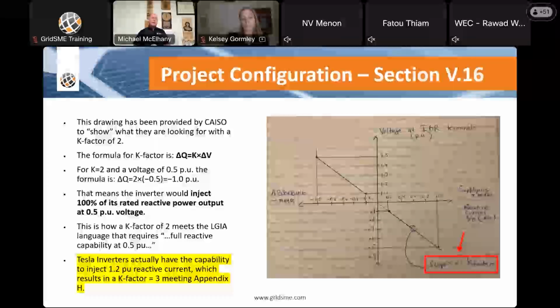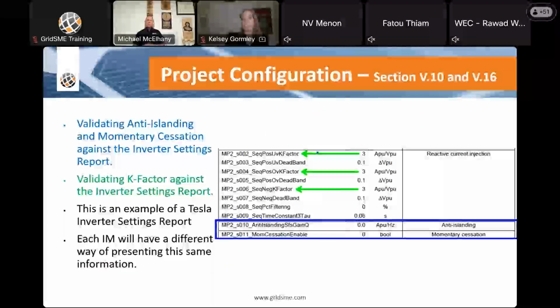The next slide has a couple of examples on how you determine whether a particular inverter has anti-islanding disabled. In this particular one, in the blue box on the bottom, it's got anti-islanding with a 0. That means it's disabled. Momentary cessation has got a 0. That's disabled. With other inverter manufacturers, you have to disable frequency anti-islanding and voltage anti-islanding separately. So again, every inverter manufacturer is different once we get into there.